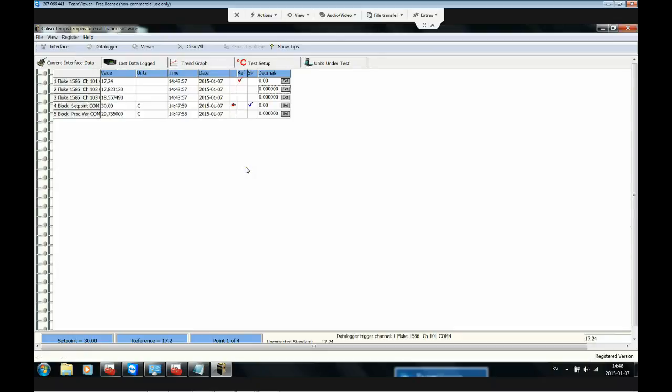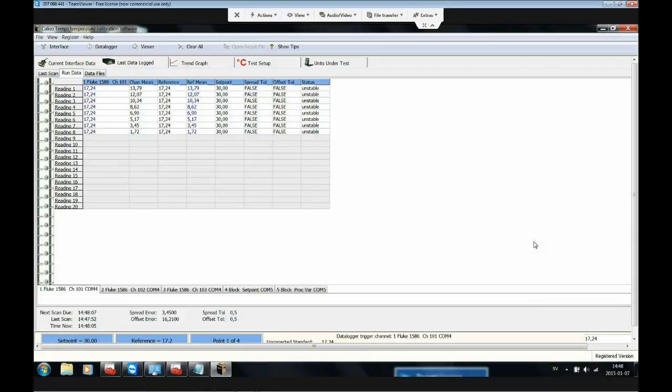So there we are. As I say, everything's now being done for you. You can sit back and relax. Let Calisto Temps do all the hard work, and when it's done, we'll just create some calculations and make a calibration certificate for each of the channels. If you look towards the bottom of the screen, you'll see a set of tabs. Each of those is one of the channels that we're recording. So the next job is to generate the data.